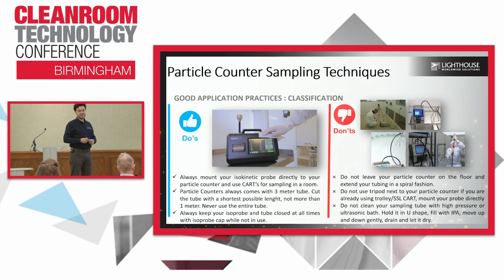And don't leave your particle counter on the floor. In most marketing material, we are still seeing particle counters lying on the floor. That's terrible. The reason is because the exhaust is also introducing a lot of particles to the ambient air. And do not use a tripod next to your particle counter like our marketing team did. You don't need it. Tripods are okay for a critical environment.